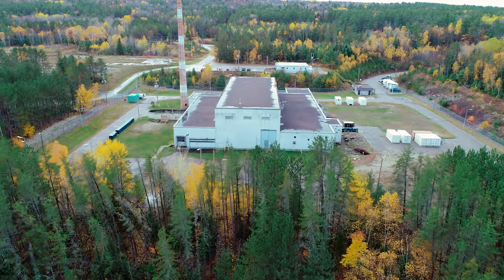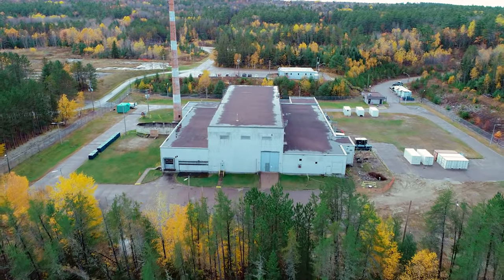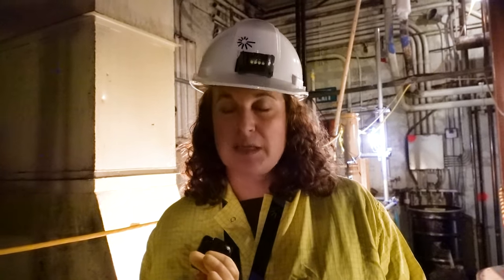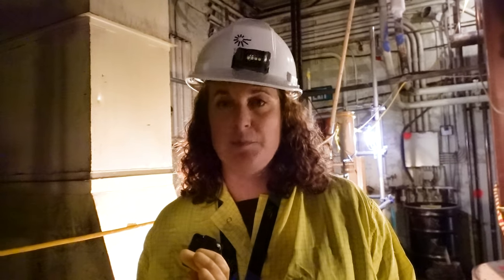For NPD, we've evaluated a number of decommissioning options and the option we're pursuing right now is in situ disposal — essentially leaving everything that's left here, all the metal components, the above-grade superstructure, which will be demolished and placed in open spaces below grade in place. We would fill up any other empty space with grout and cap and cover the facility, using the existing concrete box as a waste disposal cell to dispose of the material in place.